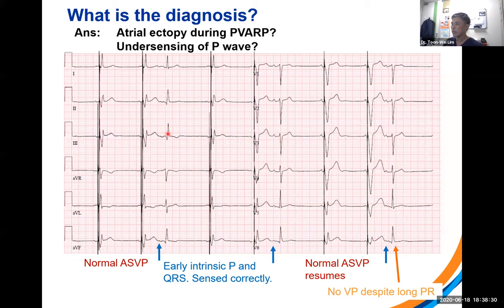However, the ventricle is sensed, and that would then delay your next atrial pacing interval. And before that atrial pacing interval times out, an intrinsic activity actually comes in, and then you get A-sense, V-pace again. So that's what I think is going on. But ultimately, you'll still need to interrogate the device to figure out what's going on.